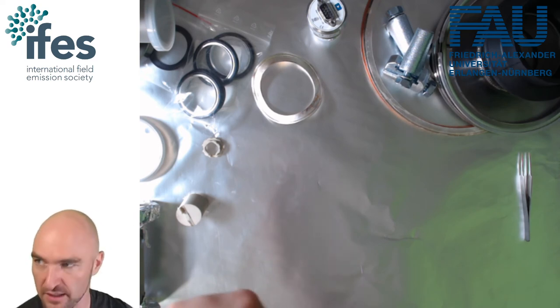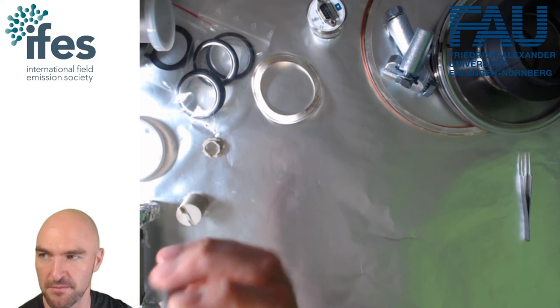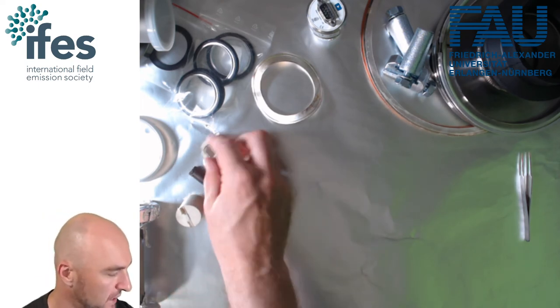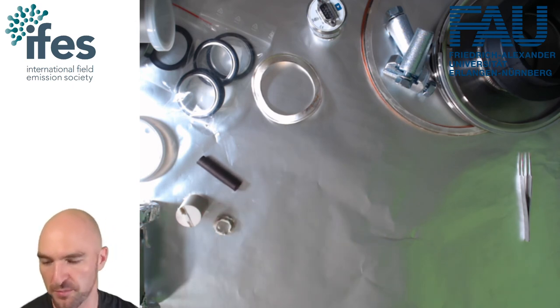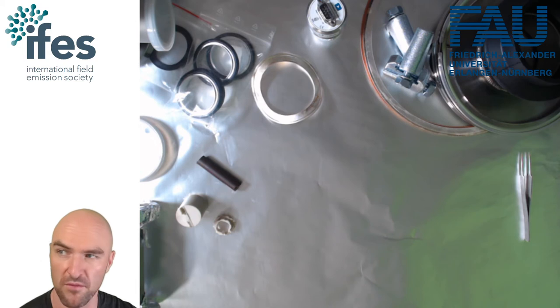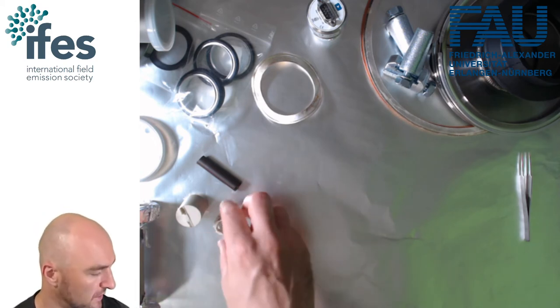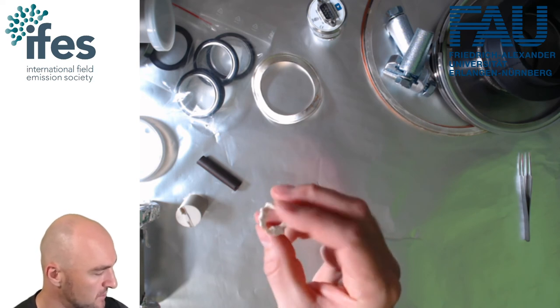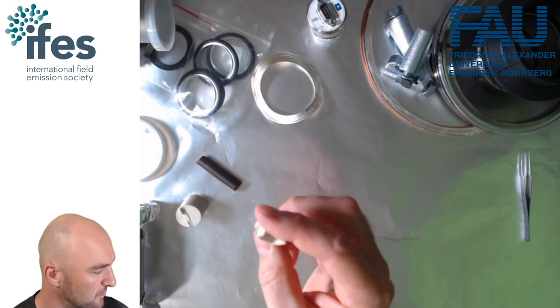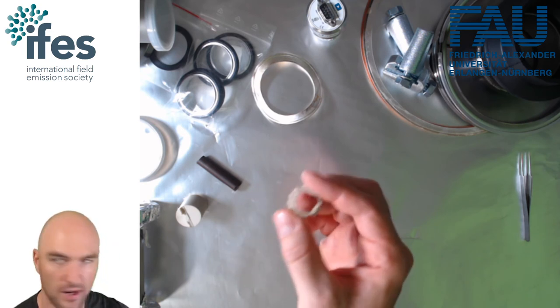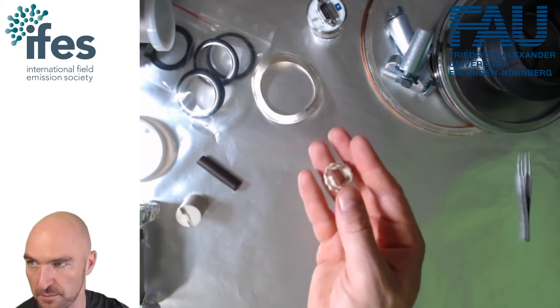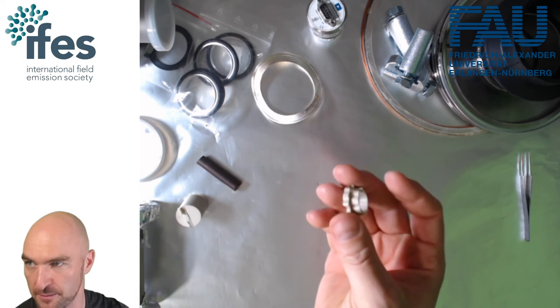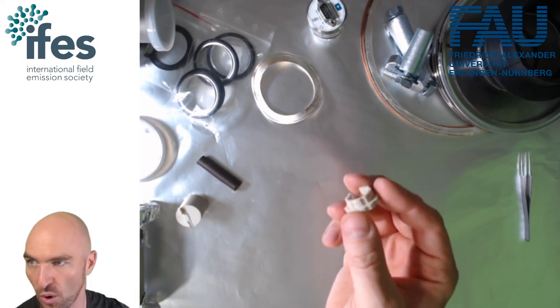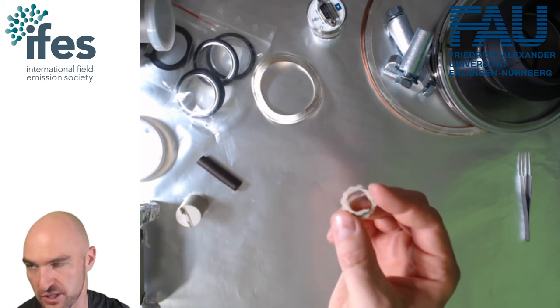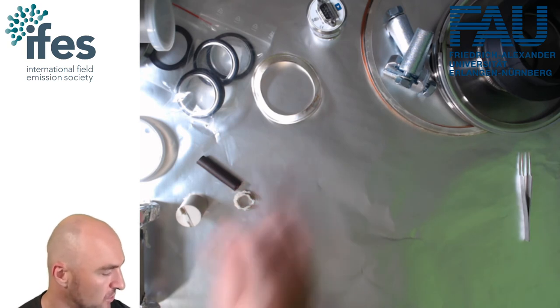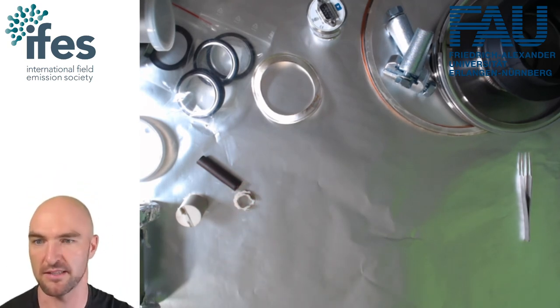But it also has a high strength. It has a strength comparable to aluminium. And it's easy to machine. And you can bake it to fairly high temperatures. As I've mentioned before, with polymers, the important thing to remember is the more polymer volume you have in there, the more moisture you have inserted. That's why very often, this is actually a piece where I made a mistake, but this is what would, for example, be a spacer for a buffer chamber carousel. And you can see that we've put a lot of machining in so that we reduce the volume of PEEK, or the volume of polymer, as much as we can, and thus also reduce the amount of contamination you get into a system as much as we can.